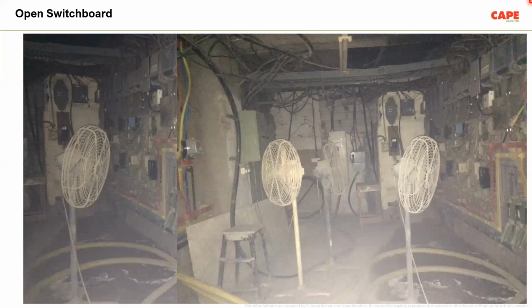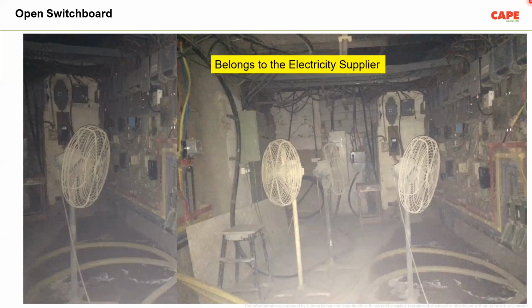This was in 2015. Even in 2017, this installation existed. I don't know the current situation. Now, when we met the owner of the building, we asked, why are you keeping it in such a bad situation? Then he told us, no, this belongs to the energy supplier, the electricity supplier. I was actually shocked to see this kind of installation made by the energy supply company, the electricity board or the utility, inside the customer's premises, which is a 4-floor or 5-floor building, and this is on the ground floor or in the basement. You look at the situation, and what is funny is, look at this area, it's wet. This place is wet, and there was a smell of diesel. I suspect that the diesel for the DG is also kept inside this particular room.